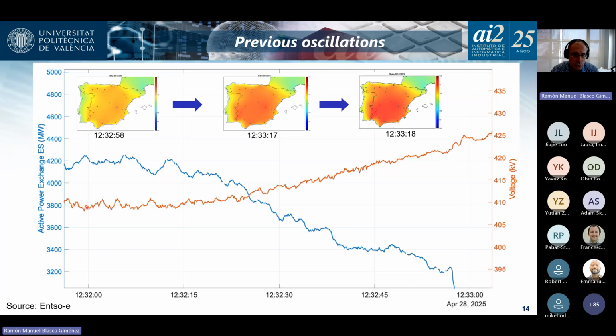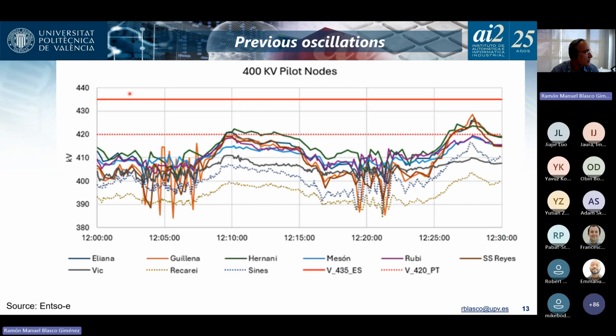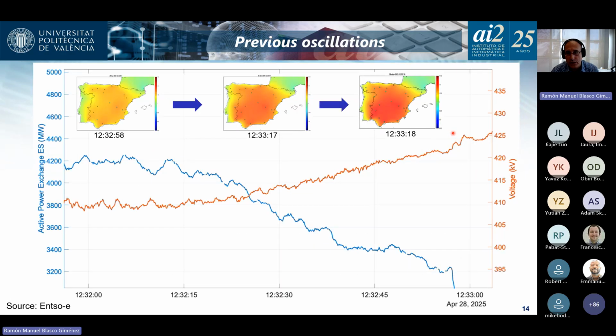Here you see again the voltage going up and the power exchange with France and Portugal, in our case, going down. Initially voltage goes flat at 410 and it goes up to 425 by 12:33. And remember that the limit is 435, as you have here. So this is still within the limit. But this is the voltage heat map. You see again how voltage increased in just 1 second.